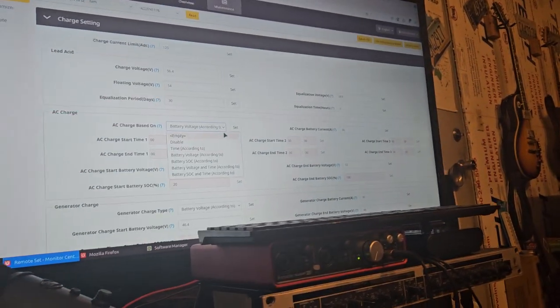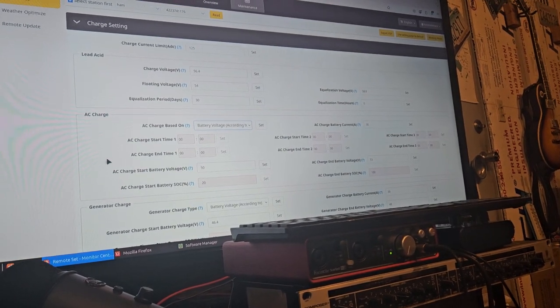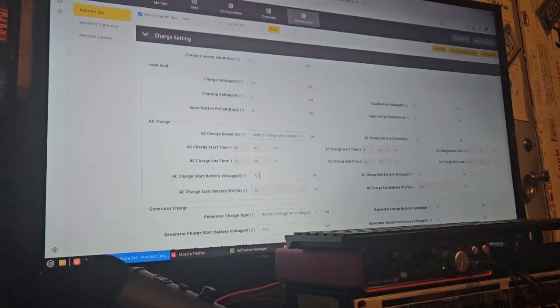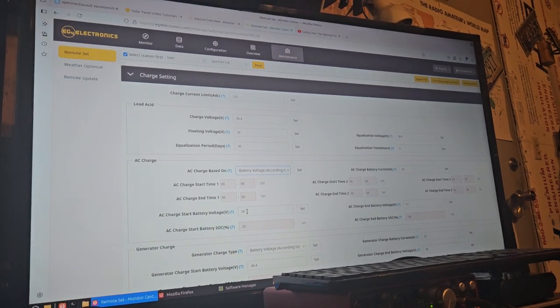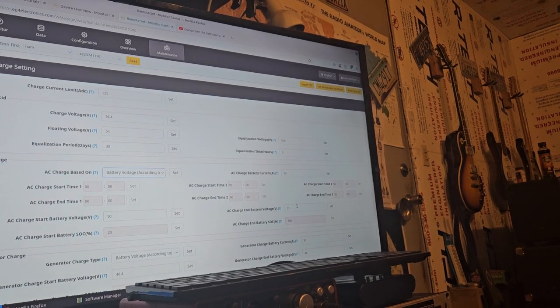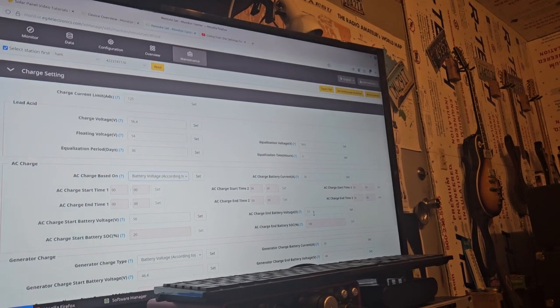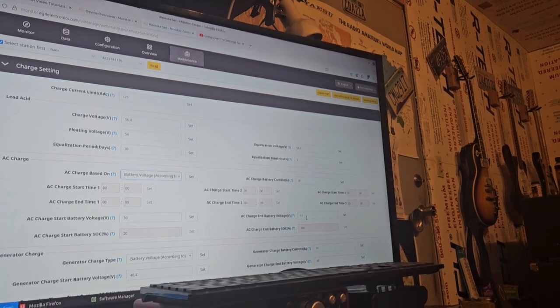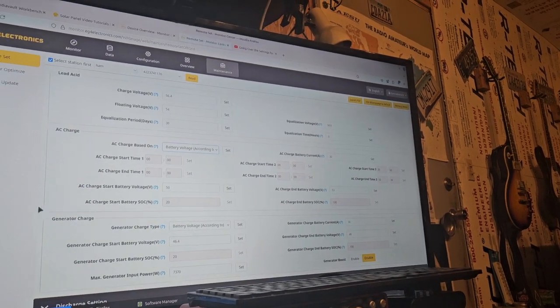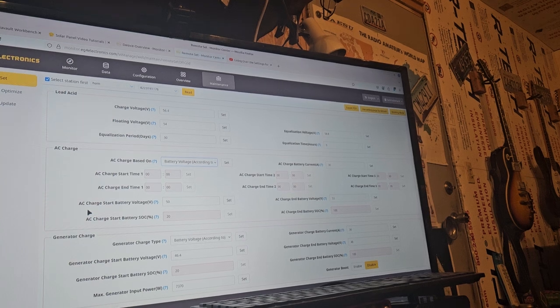So you can set the voltage you want it to start charging at. I put it at 50 volts because that's when it's already down to like 15%. And then I have it set to stop at 53, which I figure is like 80% or 60%, somewhere around there. It's just enough. I want to keep the battery up and not rely upon the grid. I want the solar to do its job.